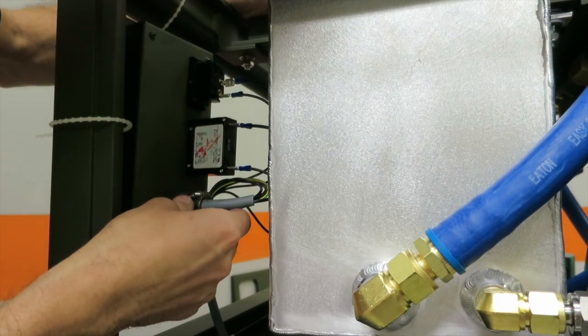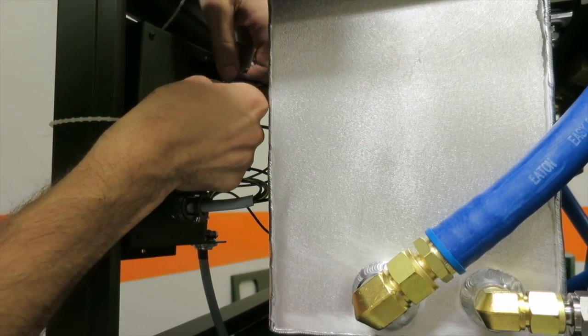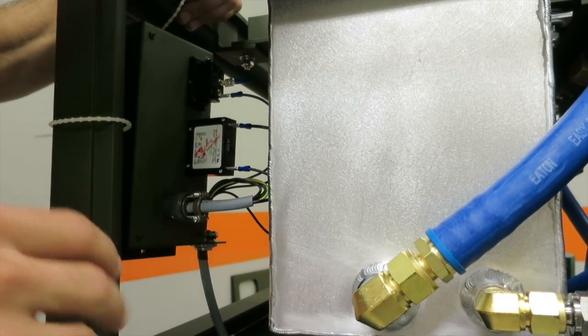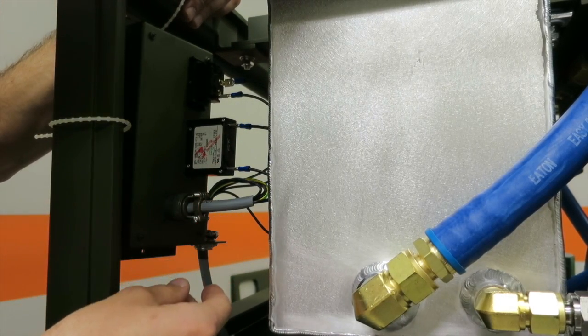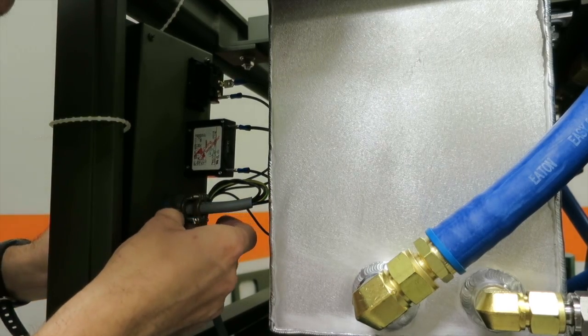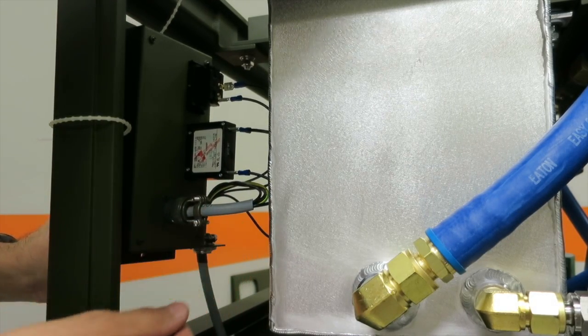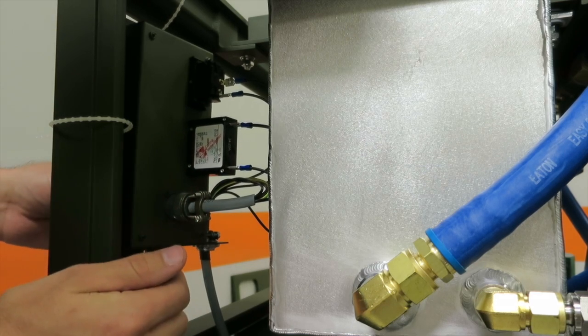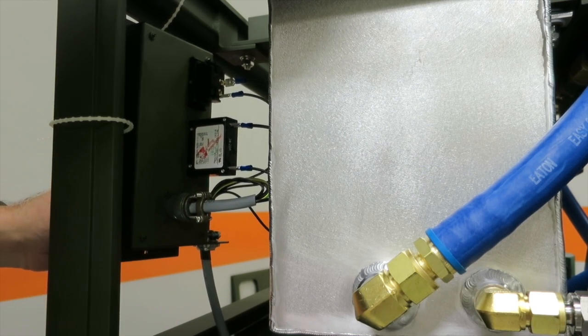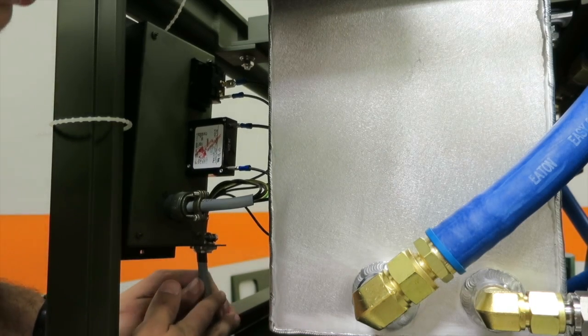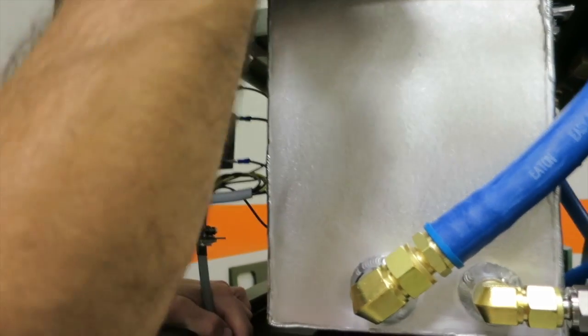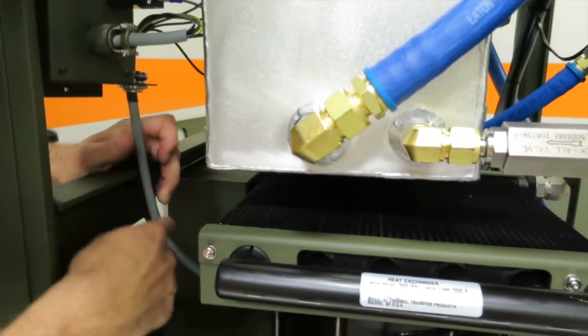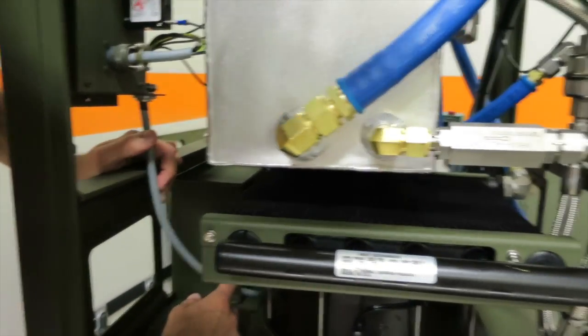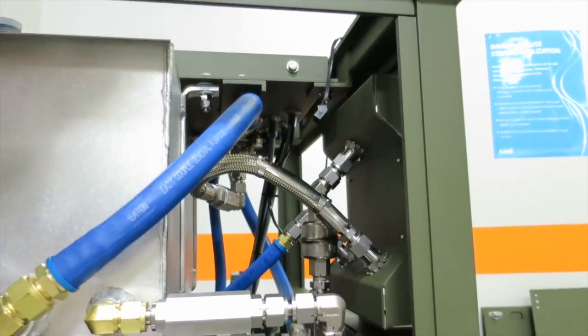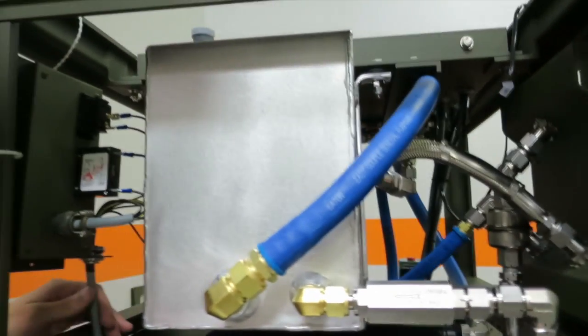When you're working on any of this, again, always have the power off, because you would have 120 on these terminals. So have it disconnected and have the power off. Right here is the power connector that goes to the sterilizer main unit. This is mounted with 4 Phillips head screws on the operator side of the panel. Those can be removed. And this cable is routed up to the electrical box on the top. So if you ever have to disconnect this, you can follow this up through the cord grip. It's in cord grip number 2, and you can remove it out of the electrical panel.